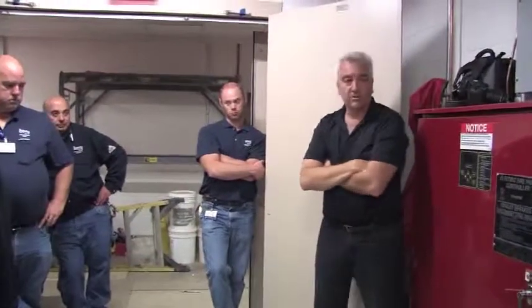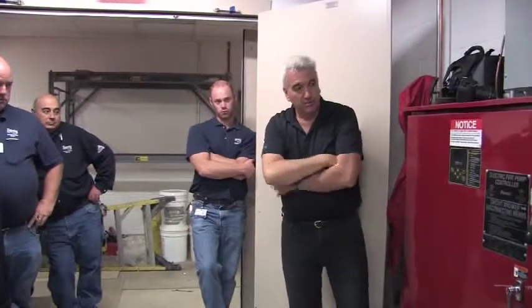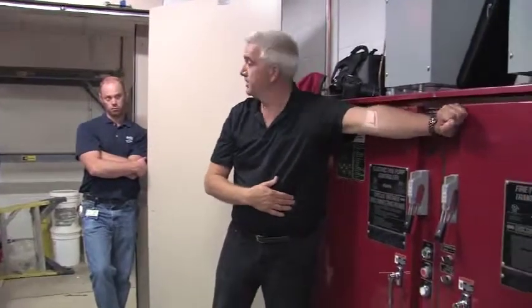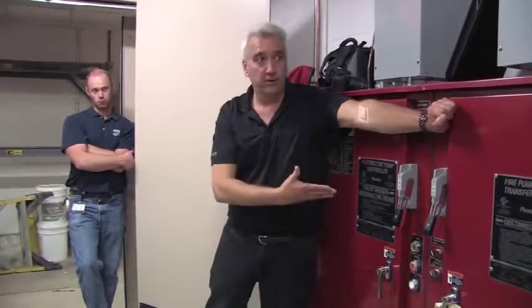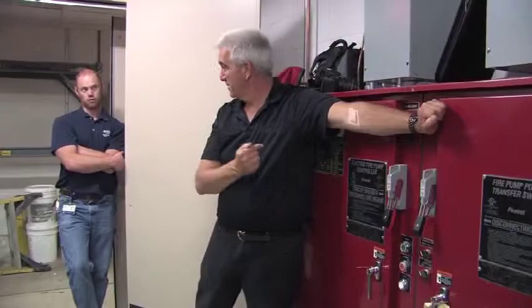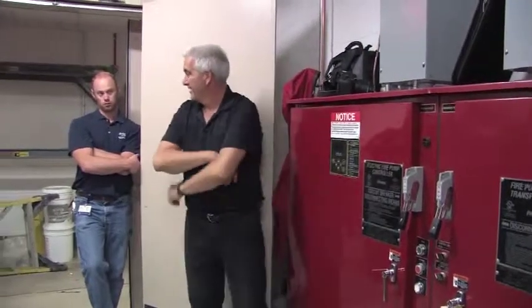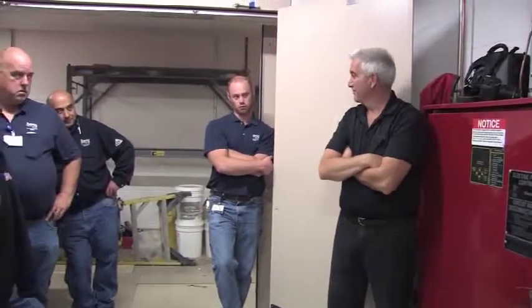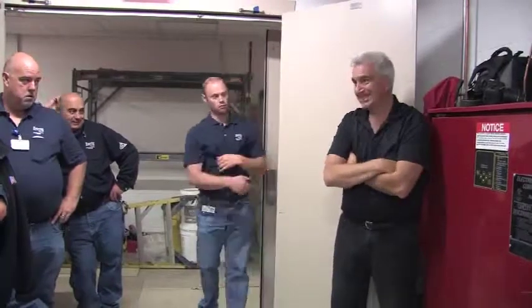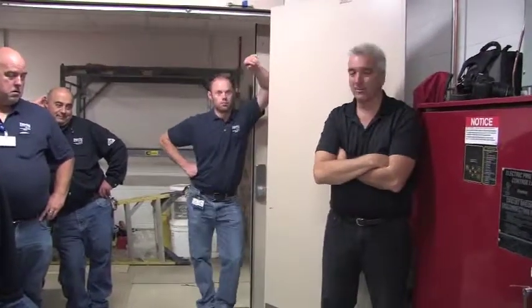Code says you have to have emergency power available up here within 10 seconds. It doesn't have to be switched over, it doesn't have to be running, but you have to have power available at 10 seconds. A lot of people will think, you're not flowing water yet. Well, you don't really need to. You have to be ready to.